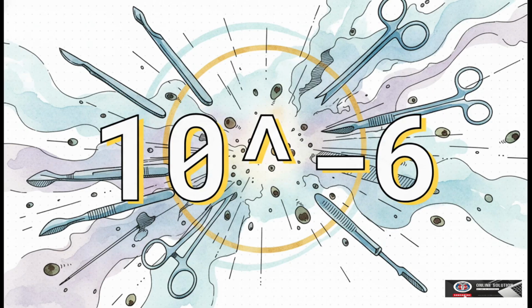We use the sterility assurance level, or SAL. Achieving an SAL of 10 to the negative sixth means there is literally less than a 1 in a million chance of a single viable microorganism remaining on your instrument. It's a mathematical guarantee of safety for your patients.